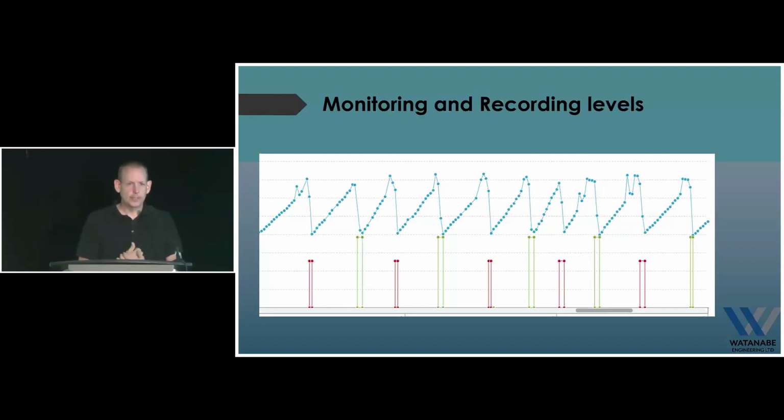Actually, I was in my hotel room last night doing exactly that. Anybody know where Kinkham Inlet is? I just put a radar transmitter and reservoir there, and I had to do a quick echo profile on it. It's like 3 days for me to get there and back, so being able to do this remotely is huge. And I get all of that data.